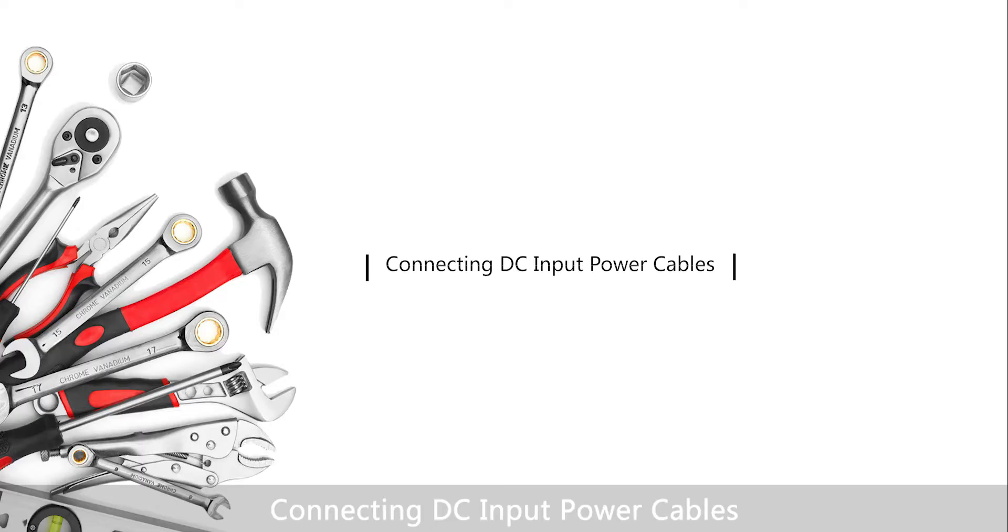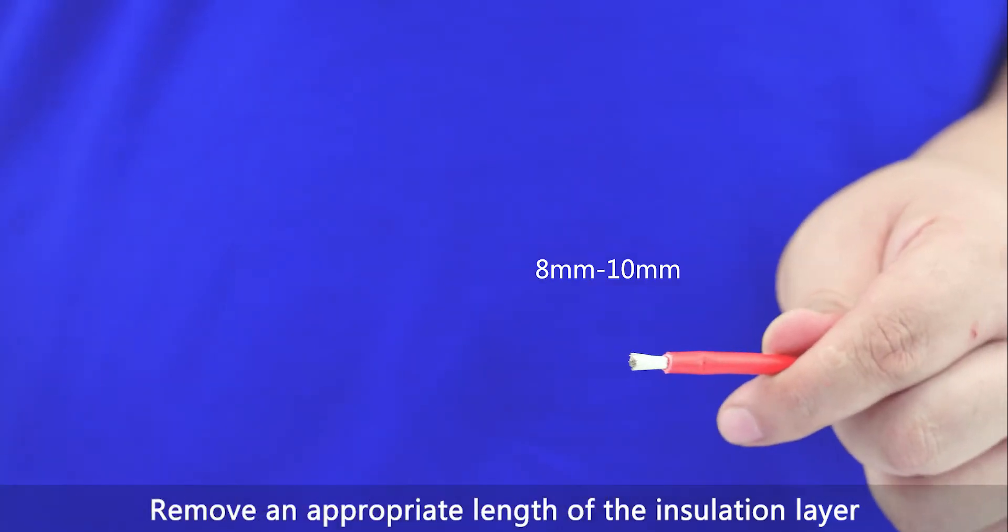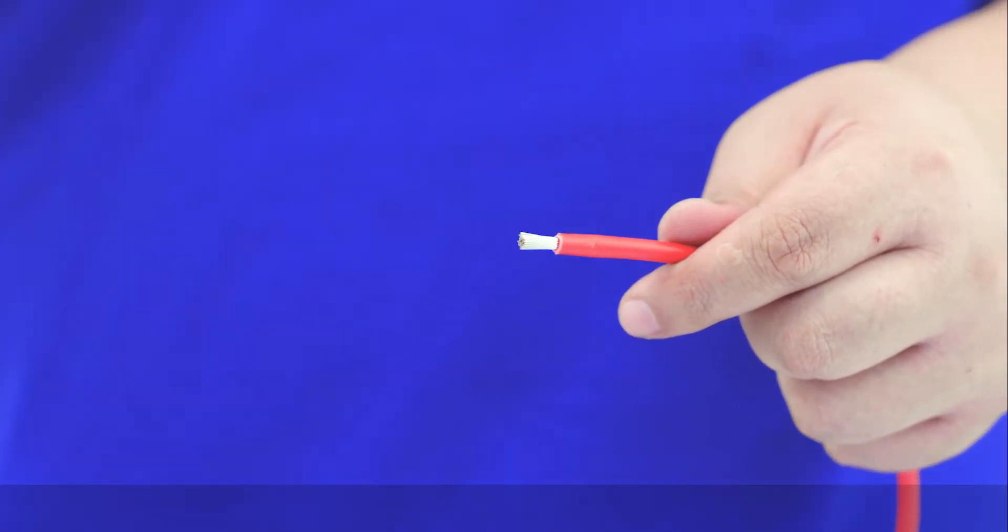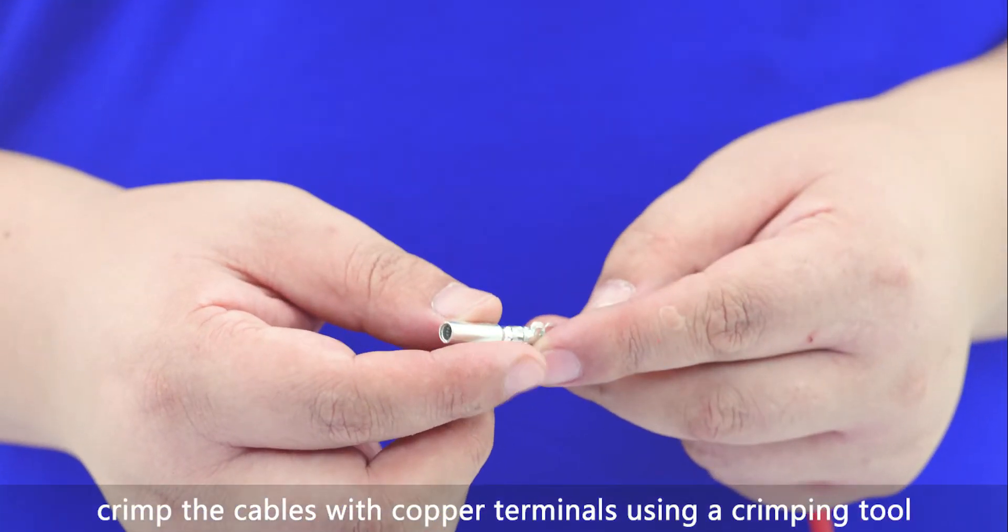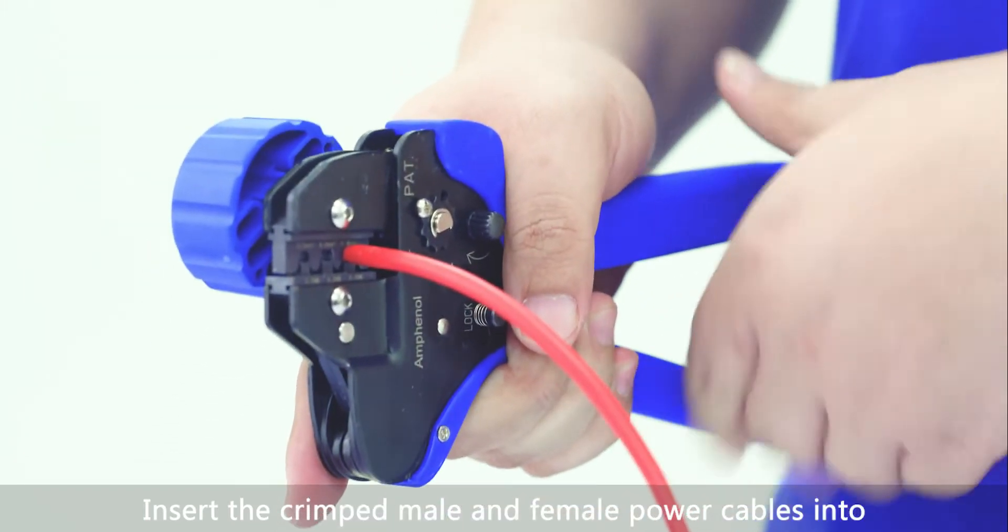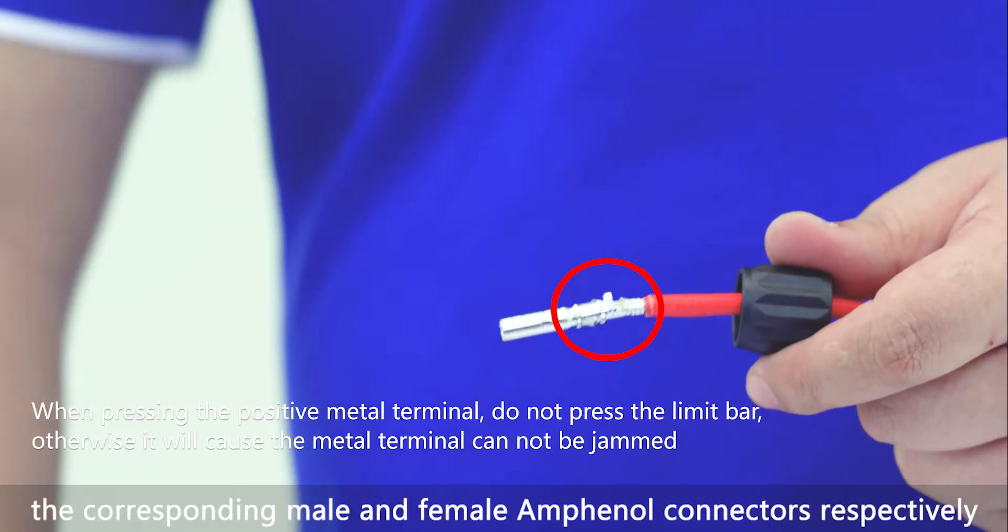Connecting DC input power cables. Remove an appropriate length of the insulation layer from DC input power cables using a wire stripper. Crimp the cables with copper terminals using a crimping tool. Insert the crimped male and female power cables into the corresponding male and female Amphenol connectors respectively.